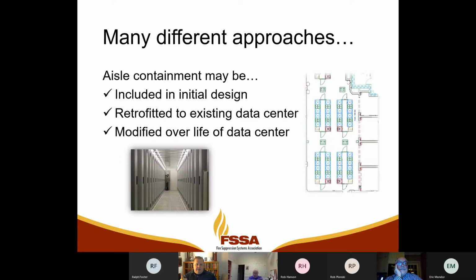Aisle containment. This is important if you're managing existing facilities and consulting for them. Aisle containment could be included in the initial design, planned for, accommodated for. It could be retrofitted into an existing data center. This is very common. There's a lot of data centers out there that are underprotected because aisle containment systems have been retrofitted into them, and there's not been accommodations for the fire protection systems because of that, or modified over the life of the data center.